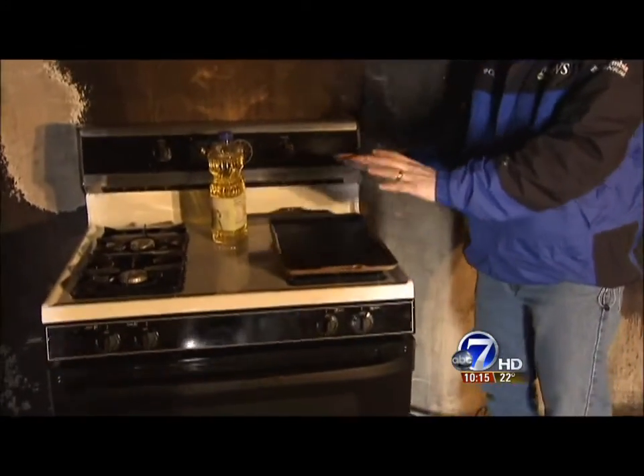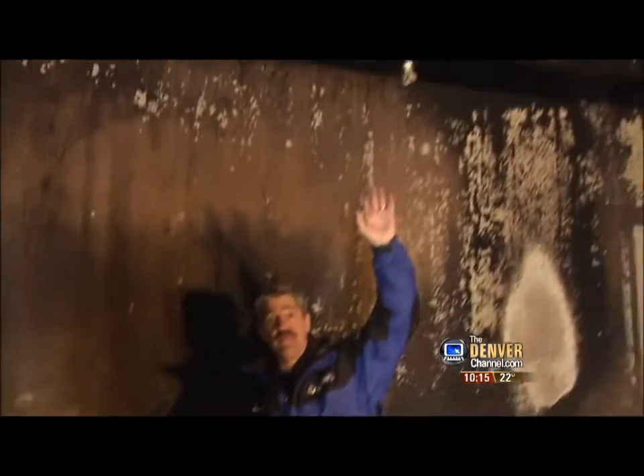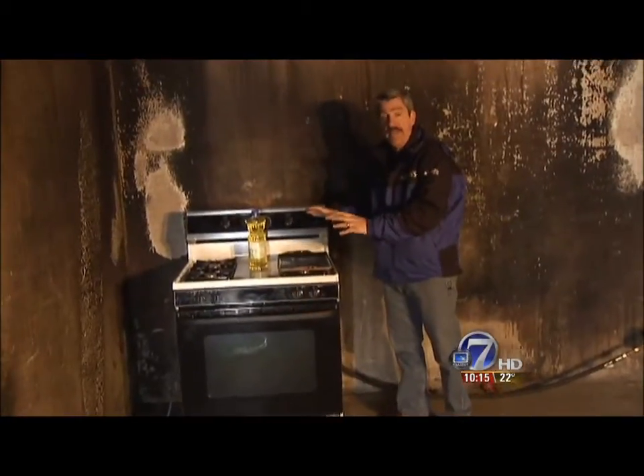For the purposes of our test, we've got a stove here with a hot griddle and some grease on it. We're going to see what happens when it catches fire. Right here we have the sprinkler nozzle where the solution is going to come down over the stove to see if we get a flash. We've set up cameras in several places so you're going to get a good look at what happens.